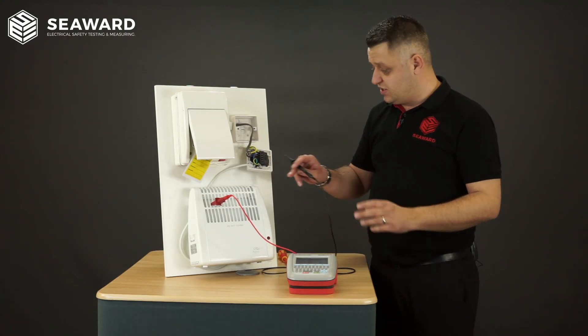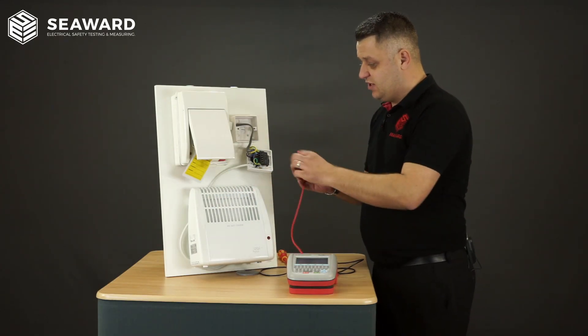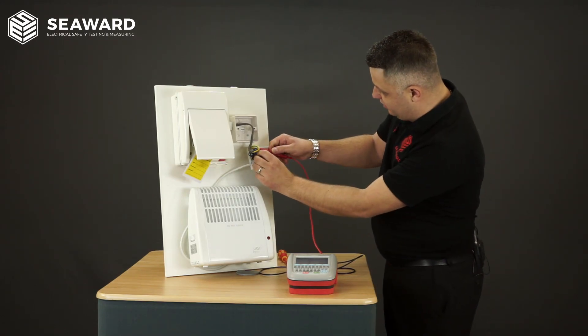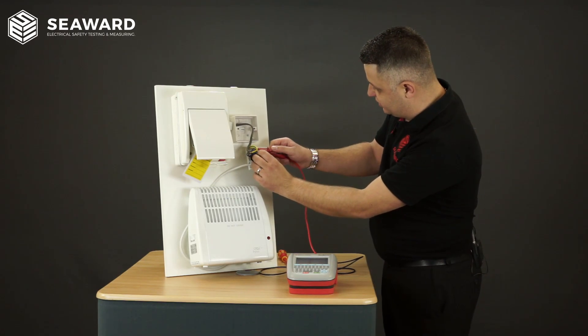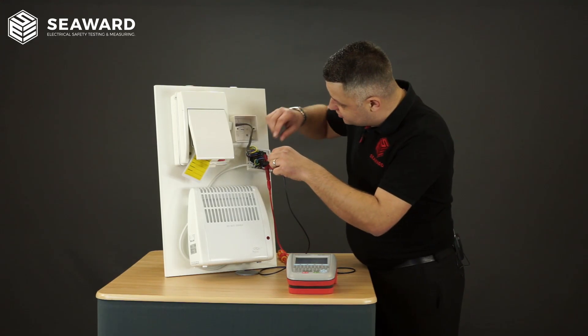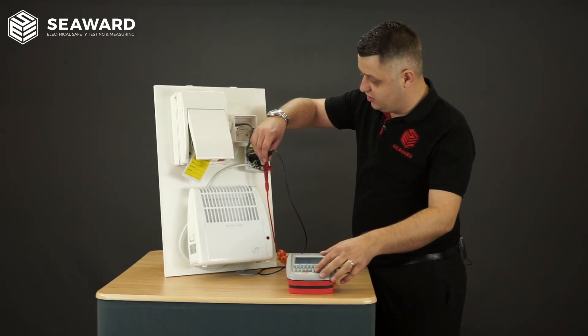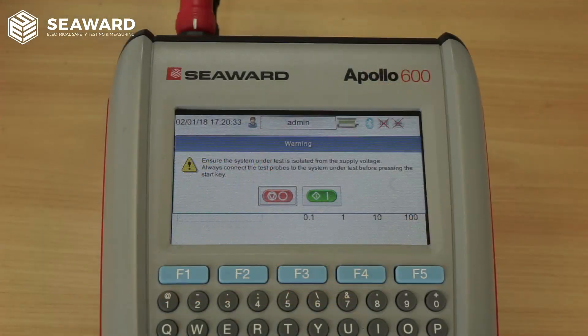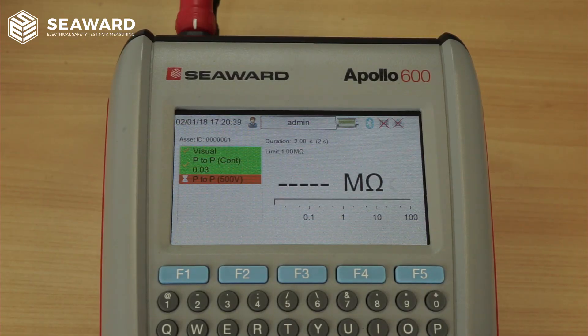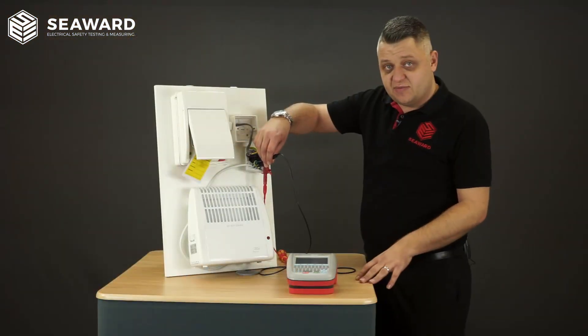We're now ready to commence with the insulation resistance test. To do this, with my test probe I'm going to link the live and neutral conductors together to make sure I've got a good connection there, and then again with the test probe going to exposed metal parts on the fused connection unit. The test has prompted me to ensure the test is safe to commence, so I will hit the test key and carry out my insulation resistance test. That's now completed and the electrical safety tests have passed.